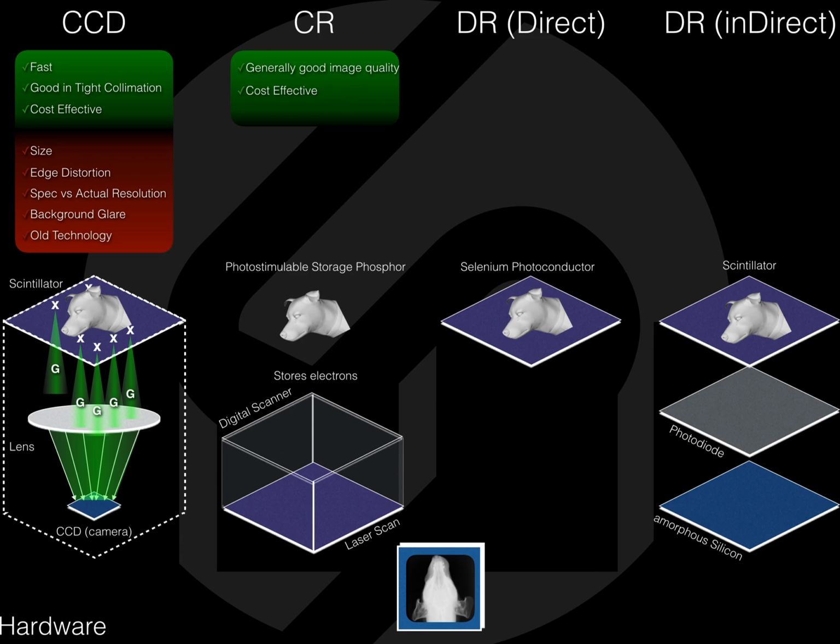An advantage of CR systems is the image quality, which is generally comparable to other digital modalities. Also, being relatively lower priced systems, the quality for the money is very good. There are, however, several disadvantages of these CR systems. The two-step process, that is first exposing the patient, then carrying the detector to the scanner to be acquired, is reminiscent of film.